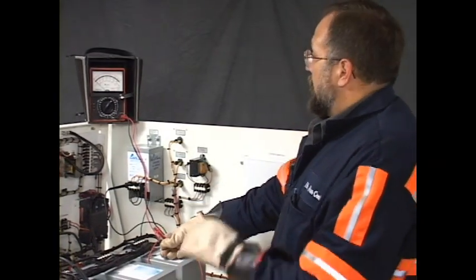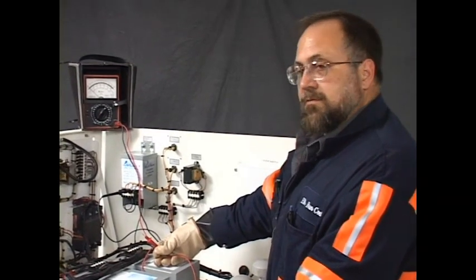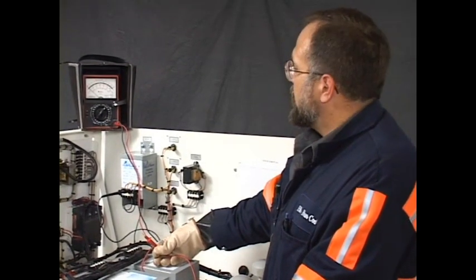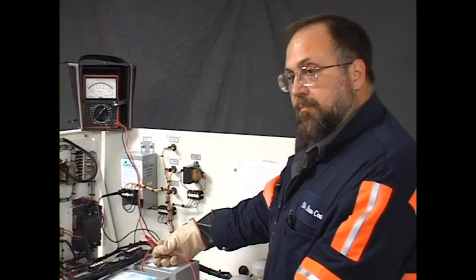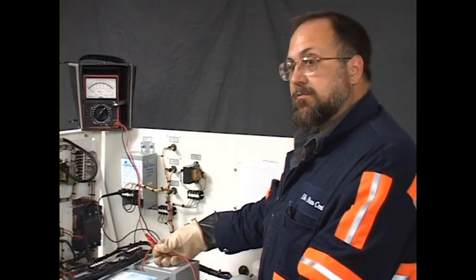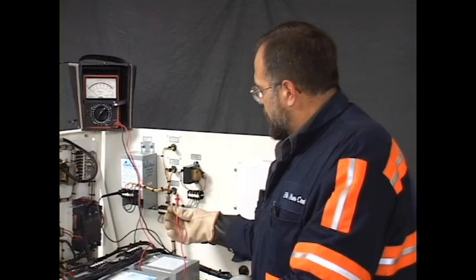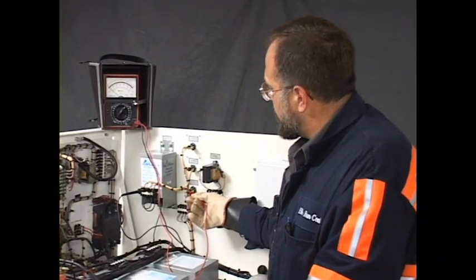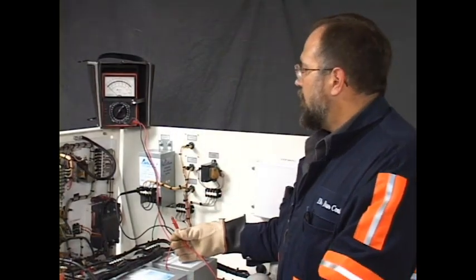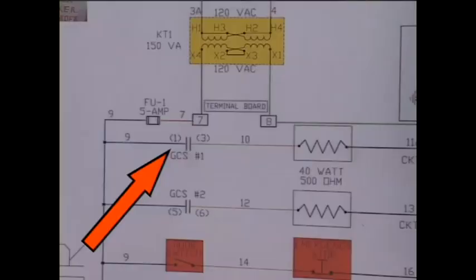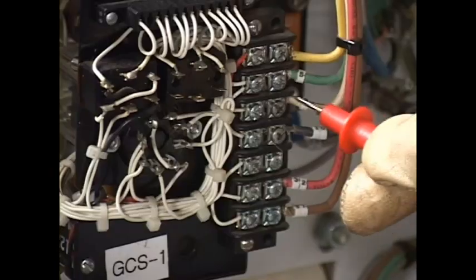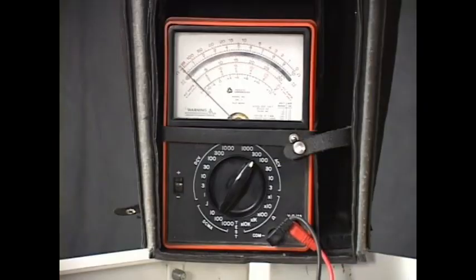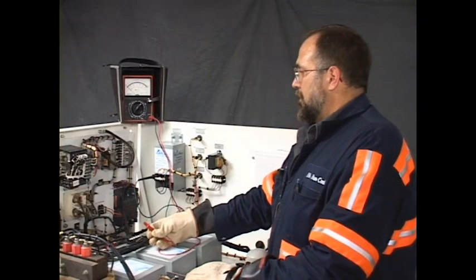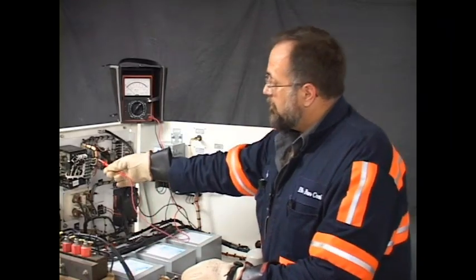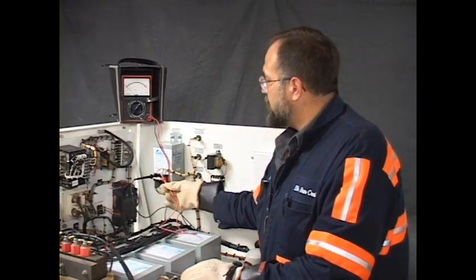Keep in mind, a voltmeter reads differences in electrical pressure. If both probes are on the same potential, then it will indicate a difference of 0. And that's what we have here, a difference of 0. From wire number 9, on the load side of the fuse, the next point I find it is terminal 1 on GCS 1. Again, I read 0. There's a 0 difference. For all practical purposes, electrically, this point here and this point here at the source are the same.